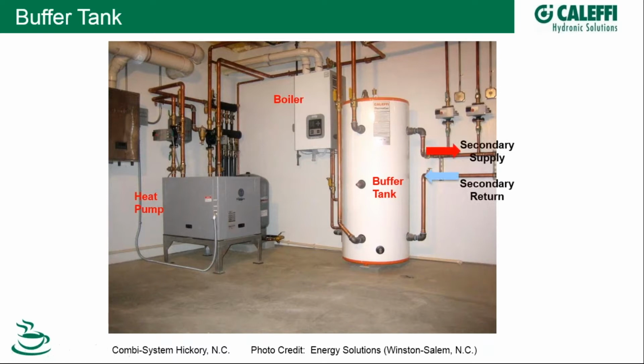So the flow is this: secondary out, secondary return. The heat pump comes into one of the top connections and out from the bottom, and same thing with the boiler. The Caleffi buffer tanks have multiple ports that allow a lot of flexibility from an installation standpoint. Now, before I leave this, just an aside: whenever you have flow coming back from a buffer tank to a heat generator, whether it's a solar collector or a heat pump or a boiler, you always want to draw from the coolest part of the tank, thus increasing the efficiency of the heat generator.